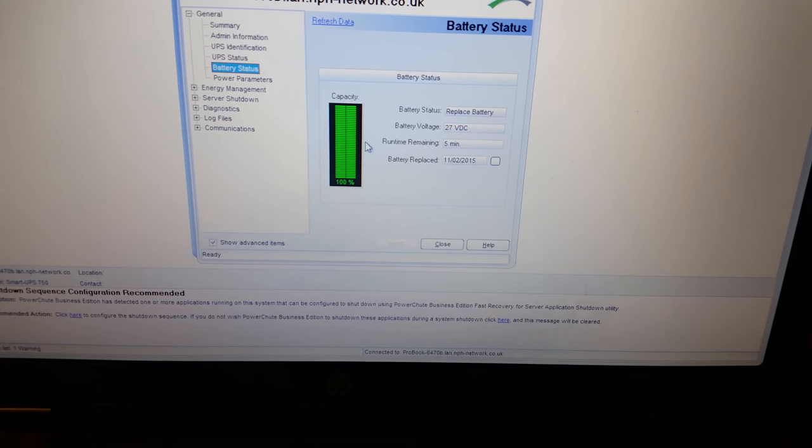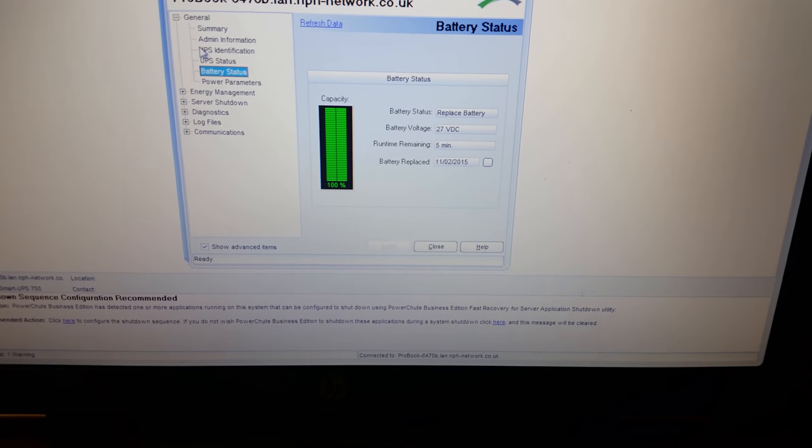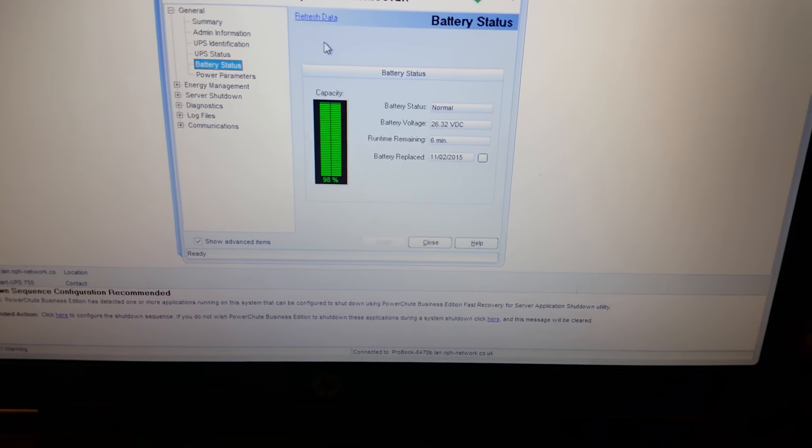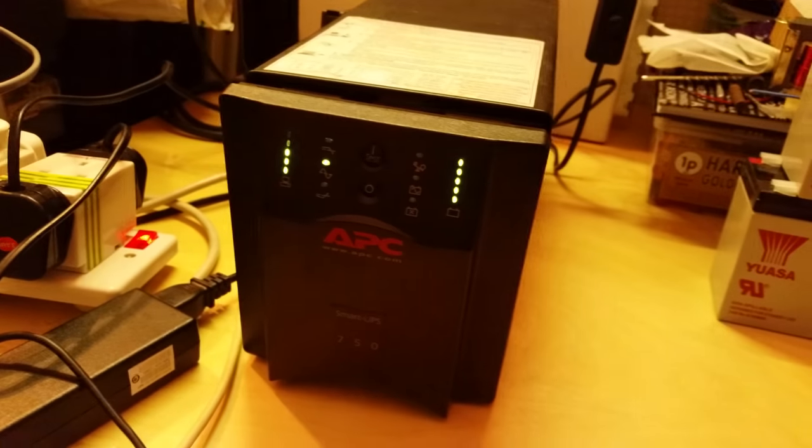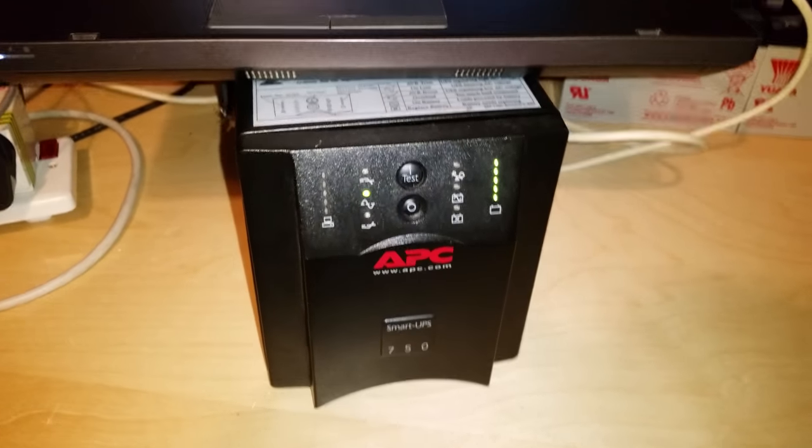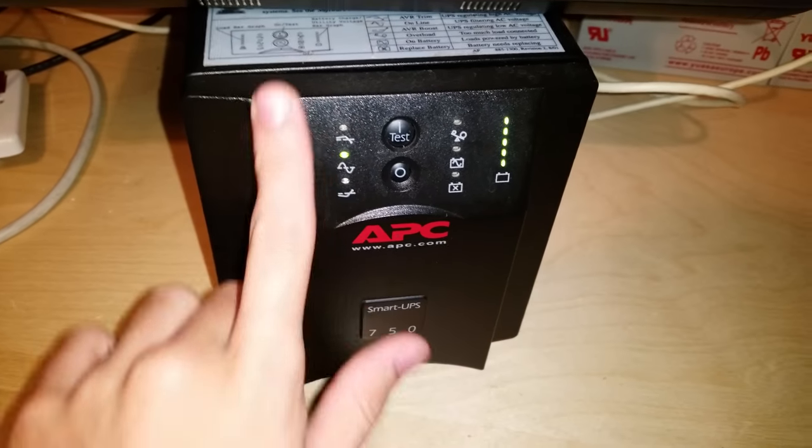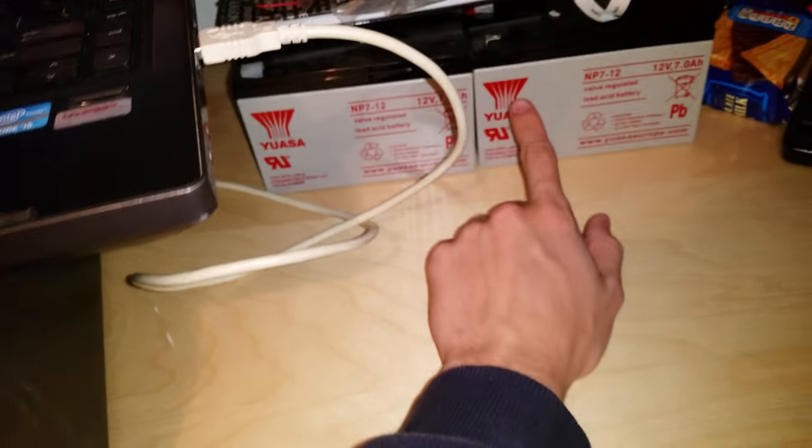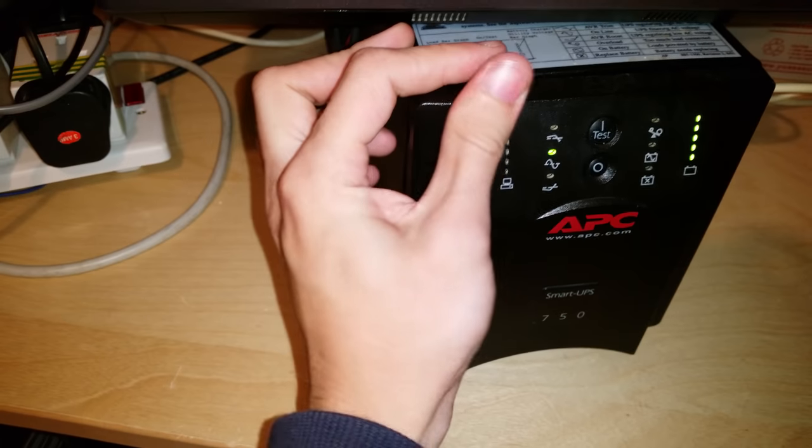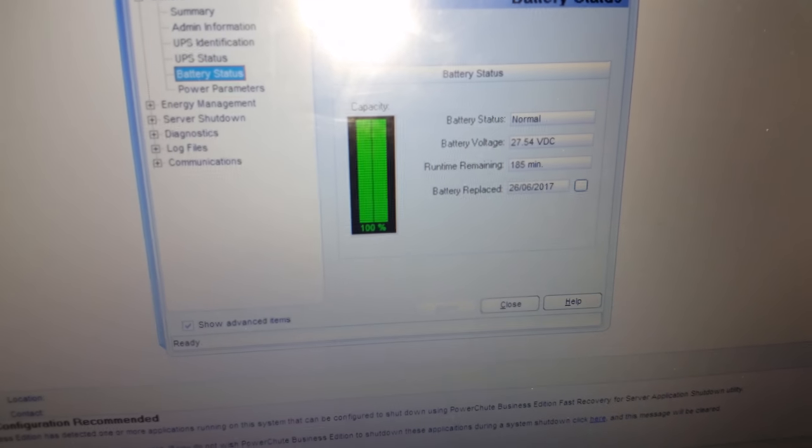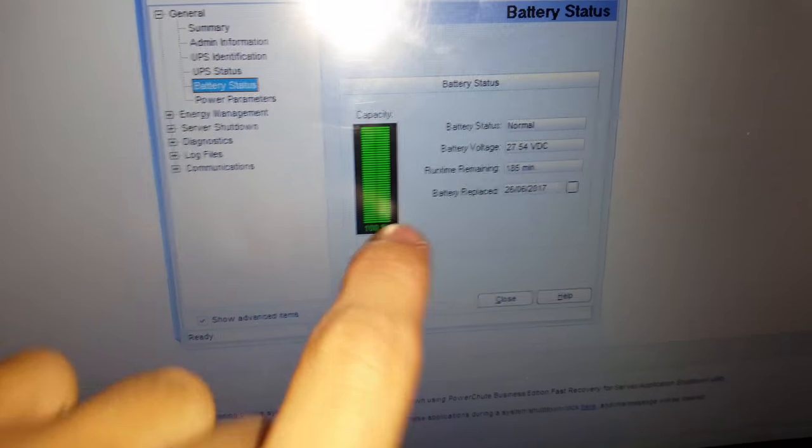Okay, I'm going to put that on later on, but let's have a look over on the computer if the status is updated. We've got online, that's all okay. Battery status, it goes to 100 percent in five minutes before this needs to be refreshed, 98 percent charged apparently. So if we let these finish charging, we can then do a rundown and calibration of it. Okay, so it's now actually the next day and this unit's charged again. It was left charging overnight and we're ready to run it down with the new batteries in. These are the old batteries here. We've got the new batteries fully charged up, it just needs calibrating. As you can see here, I just go on refresh data. You can see I've also put the battery replace date in here. Now we're at 100 battery capacity.